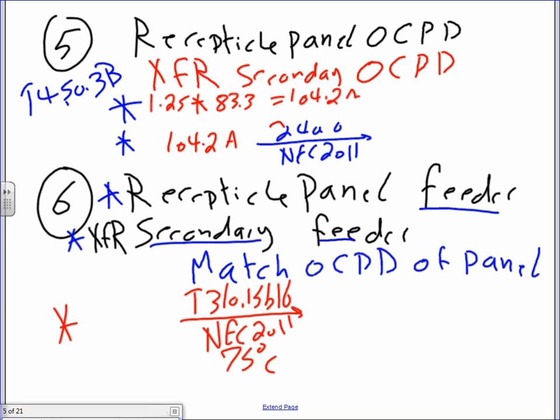Take this one to 240.6, and I hope you guys have been there. When you go there, you're going to end up with 110 amps. You can go up. You don't have to, but you can go up. You go to the next standard, which is 110. Typically it's a good idea to match the overcurrent protection device to the panel, but for the test and everything else, guys, you're going to go by this method.